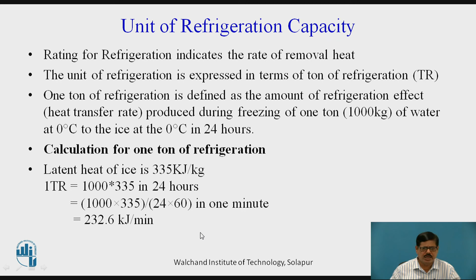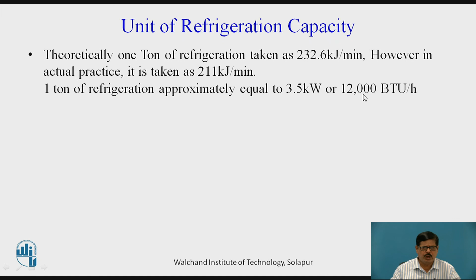But actually it is not the correct value, because theoretically 1 ton of refrigeration comes out to be 232.6 kilojoules per minute in SI units. However, in actual practice it is taken as 211 kilojoules per minute. This is the standard value. The reason is the basic unit of refrigeration has been derived from the American unit, that is BTU. Therefore, 1 ton of refrigeration is equal to 3.5 kilowatt or 12,000 BTU per hour.